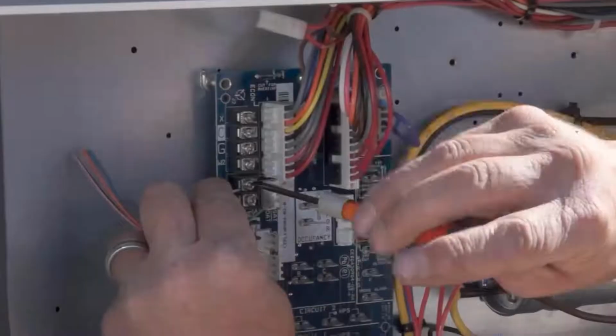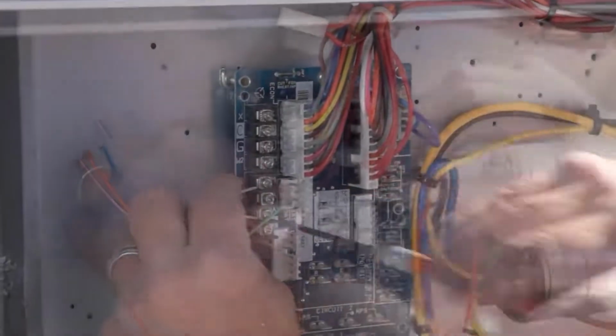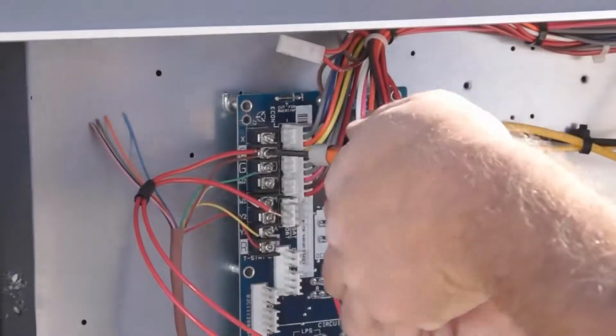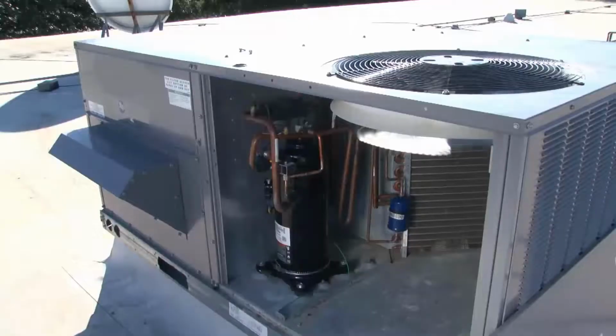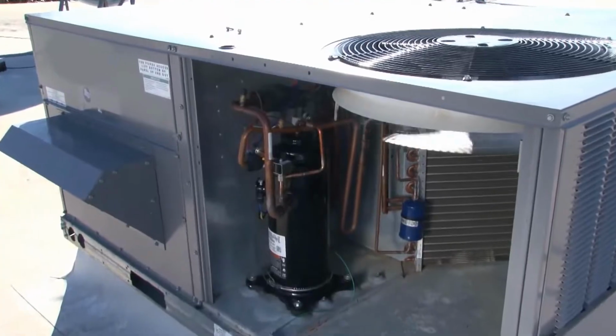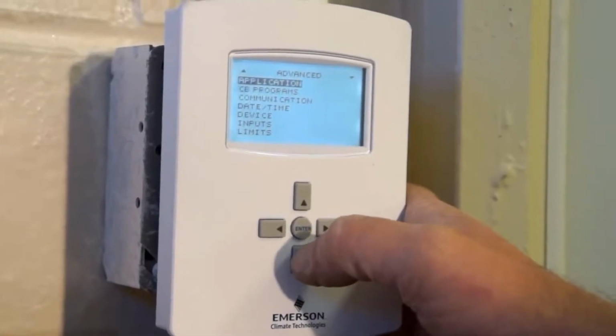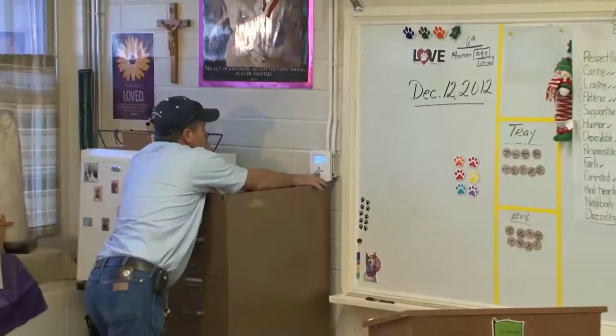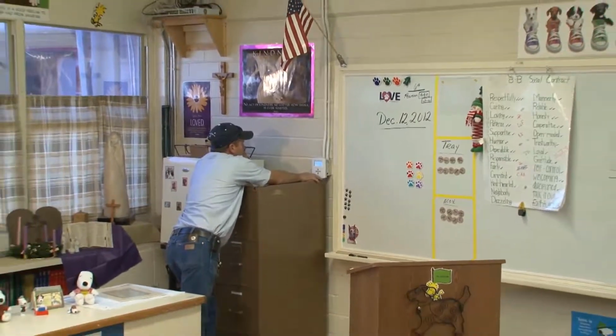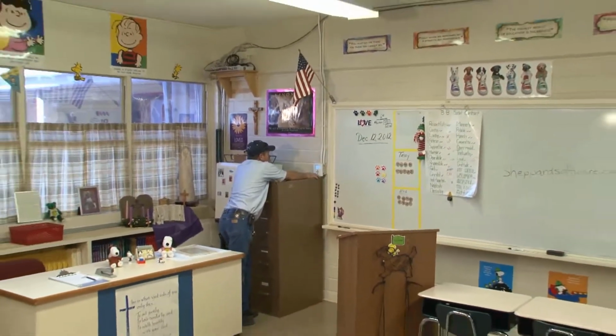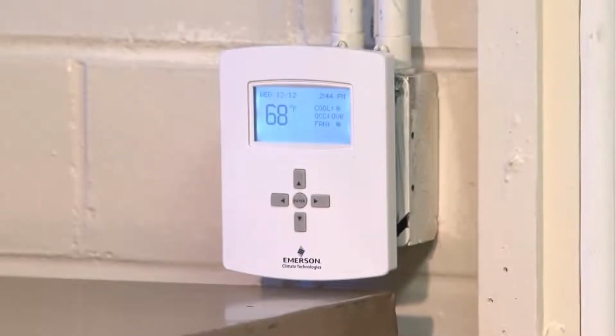Inside the unit, make the electrical connections, remembering to tie in the additional wires from the 24-volt coil. Once all connections have been made, power on the unit and program the Emerson Commercial Comfort Controller. You may need to change the settings based on the application, either rooftop or heat pump, and you may also configure the set points or program a defined schedule.